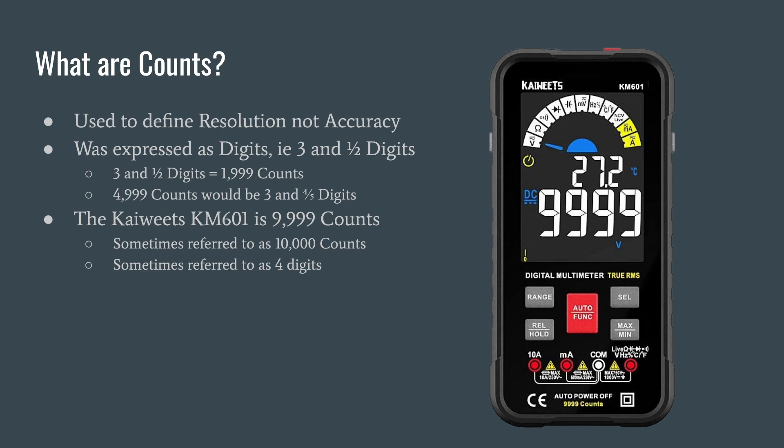The naming convention got really out of hand with no standards, so you've seen a transition in the multimeter space where folks now use counts. And even with counts it gets a little confusing. The Kaiweets KM601 says right on the meter 9,999 counts, and some marketing material refers to it as 10,000 counts. If you count one through 9,999 you have 9,999 counts; if you include zero, now you have 10,000 counts. You would also sometimes refer to this as a four-digit meter.